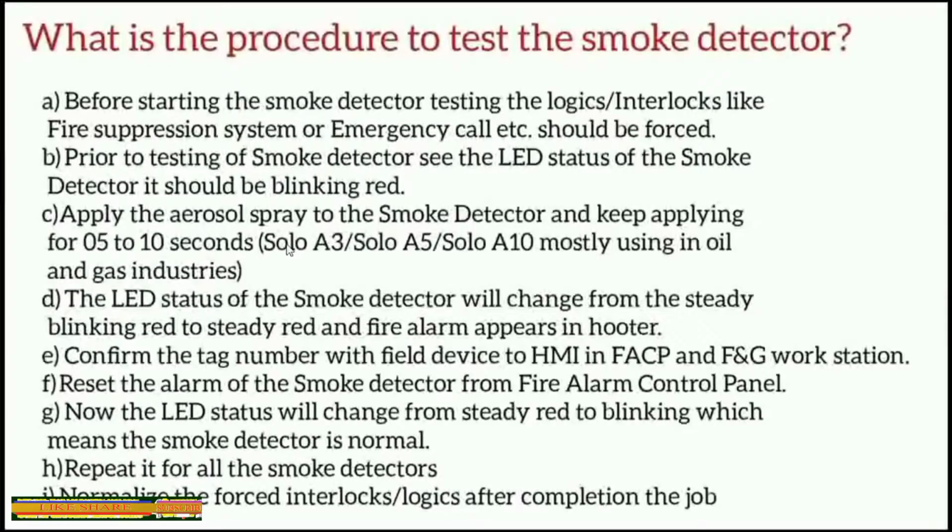Solo A3, Solo A5, Solo A10, mostly used in oil and gas industries. The LED status of the smoke detector will change from the steady blinking red to steady red and fire alarm appears in hooter. Confirm the tag number with field device to HMI in fire alarm control panel and fire and gas workstation.